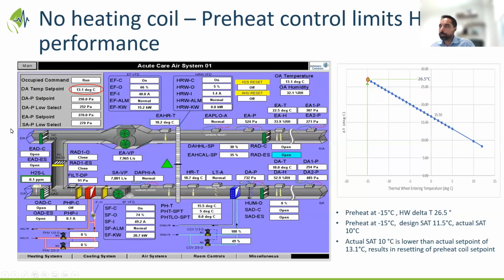Okay, this is again a unique scenario at one of the hospitals. It may or may not apply, but again, we are seeing a lot of these unique scenarios, and when you put this across facilities in the whole of Canada and North America, they become more common issues in a lot of the facilities. So what's unique in this air handling system is that they don't have a heating coil. They have a preheat coil, but they don't have a heating coil. They use the cooling coil in the wintertime to extract some of their load from the 24/7 systems to provide some additional heat rejection through this coil, but it's not enough when it's cold outside, and I'll explain that in a second.